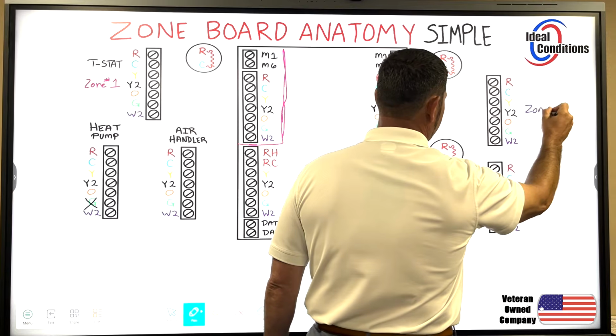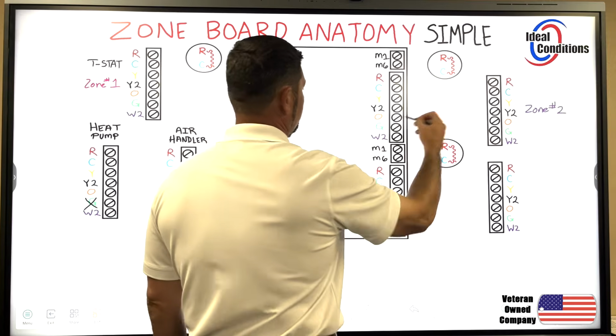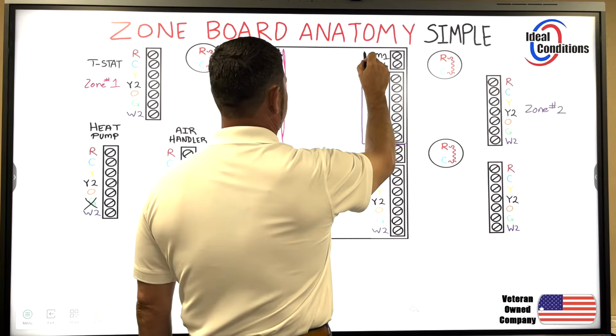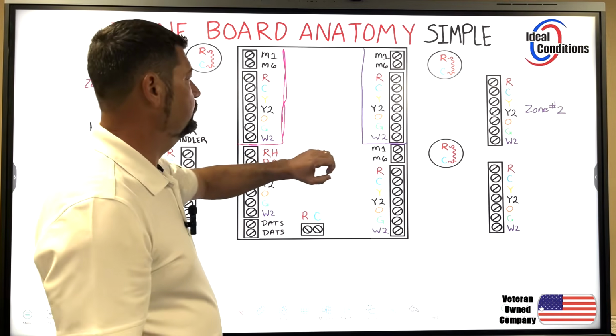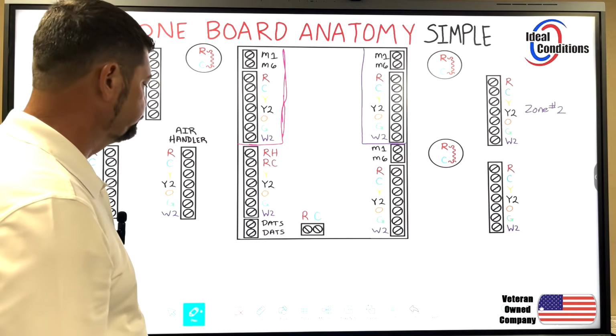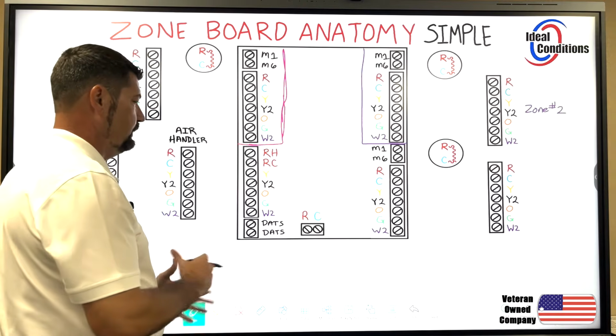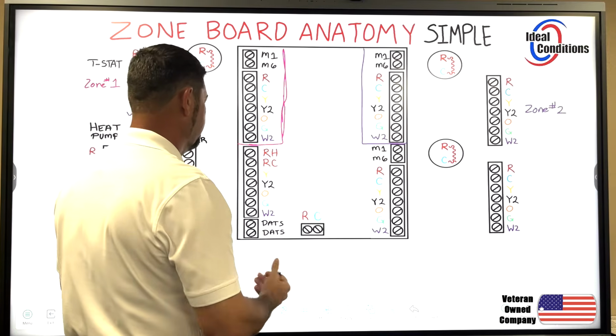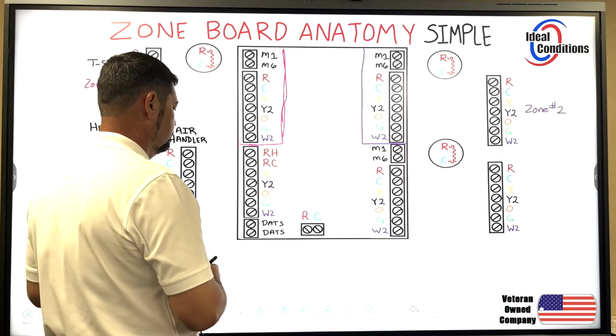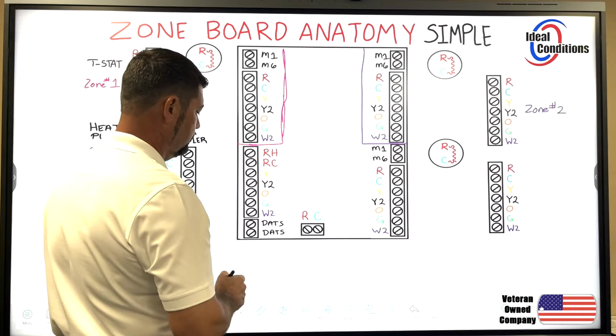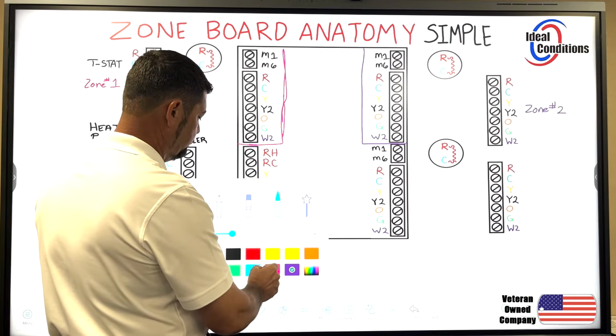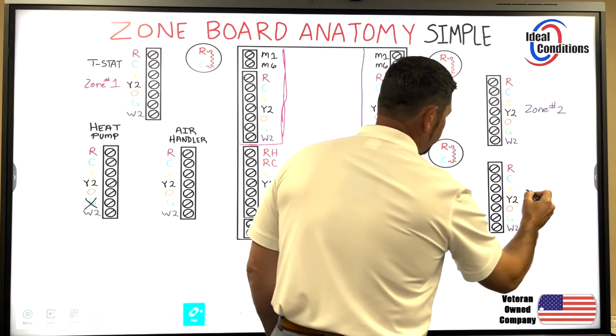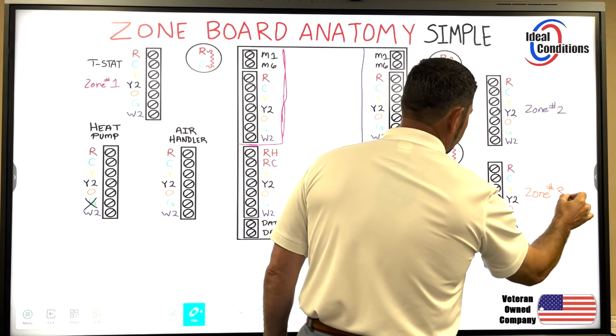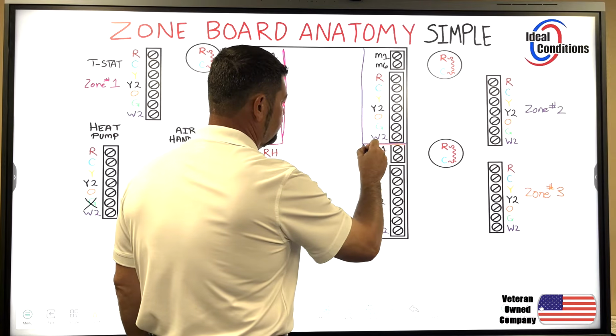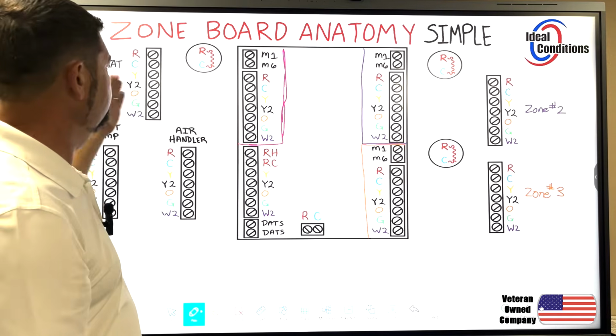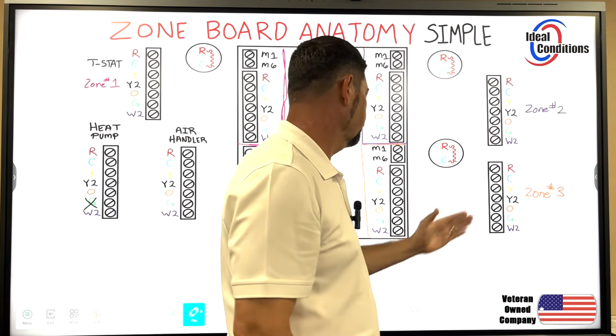We'll say this is zone number 2, and we'll call this area here zone 2. I'm not going to write zone 1 and zone 2, I've color coded it for you. You just need to systematically break down your zone board and understand where power is coming in and where the controls are going to be at that are servicing the equipment side, meaning not thermostats and dampers. We're going to come over to this last zone and go orange, and say this is zone number 3, and that's this area right here in orange. So we have zone 1, zone 1, zone 2, zone 2, zone 3, zone 3.